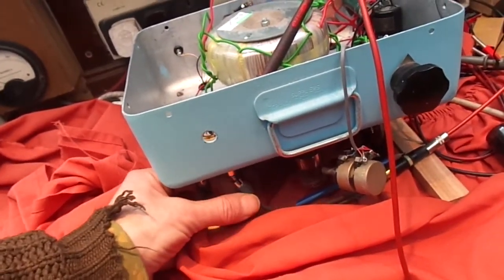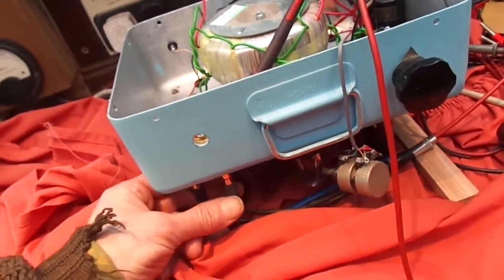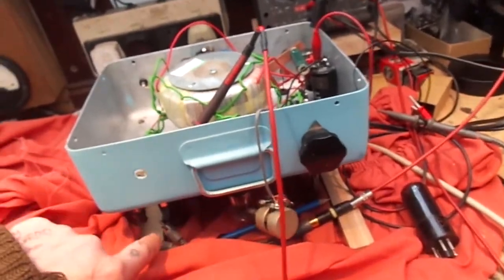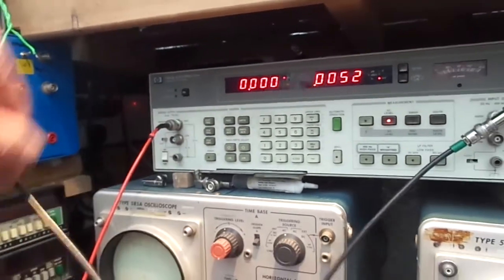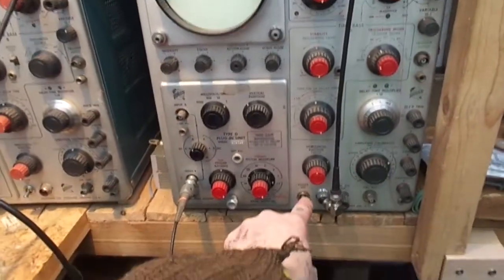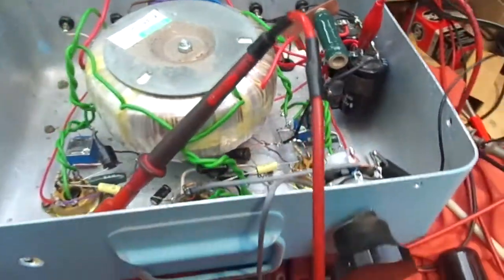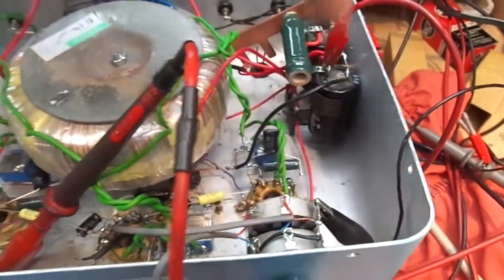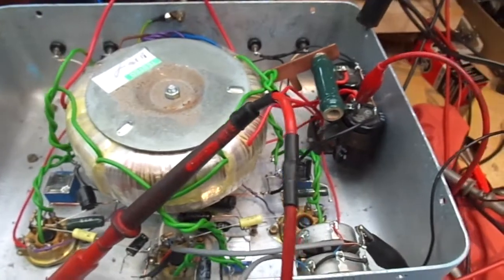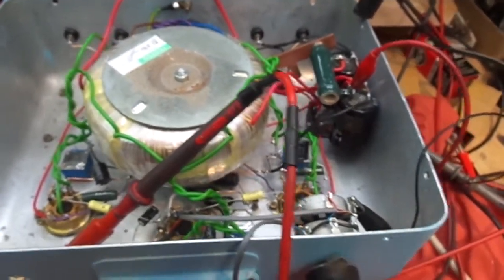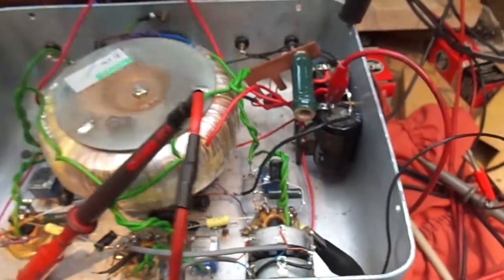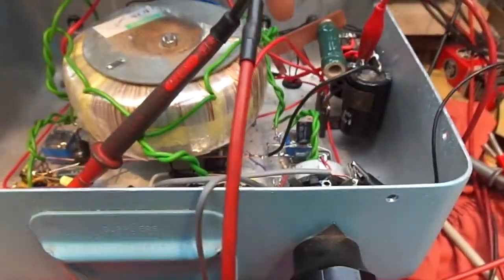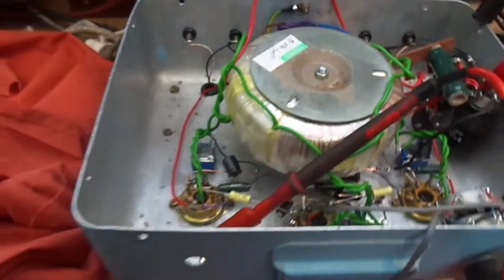But if I put the input in - I'll take that off, stop it buzzing - so if that input is in, it's going from there through the shield of this output of the HP 8903B audio analyzer to mains earth, to this mains earth, because this scope is mains earth, and back over to here. But then this ground bus here isn't going to the chassis, but this is saying it is. This is getting more confusing just when you think you're getting somewhere. Right, so look, it isn't. I know it damn well isn't. More investigation is needed.